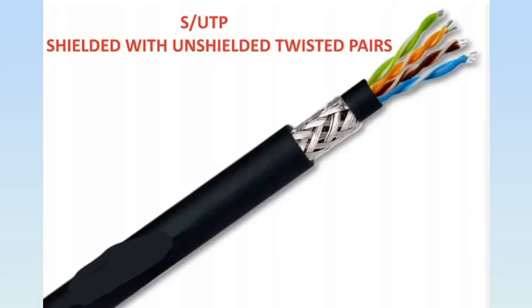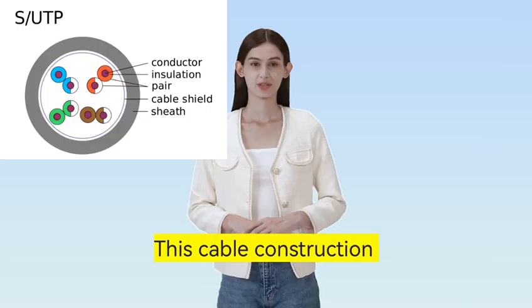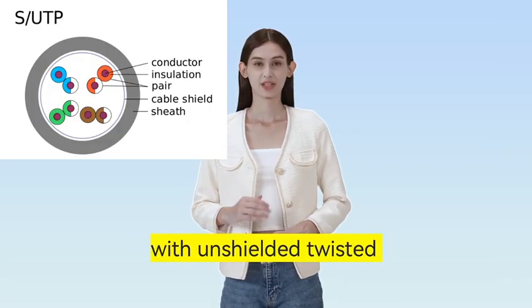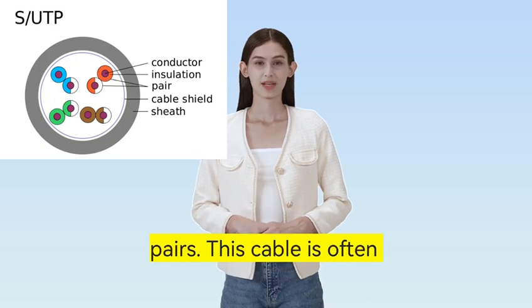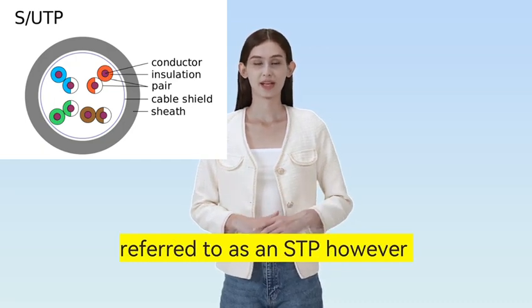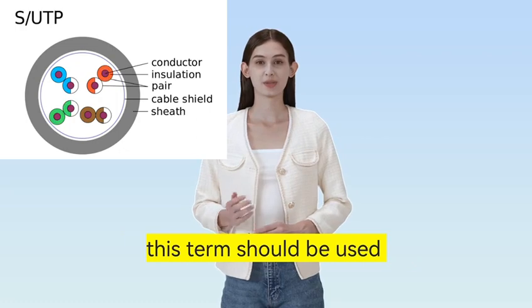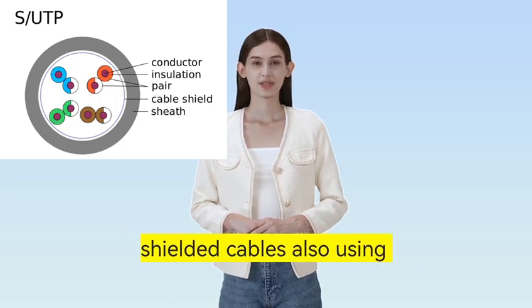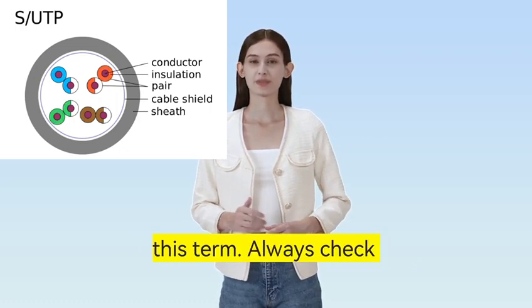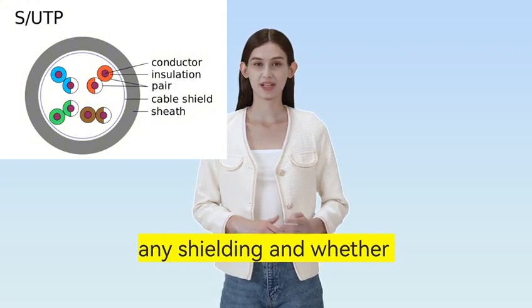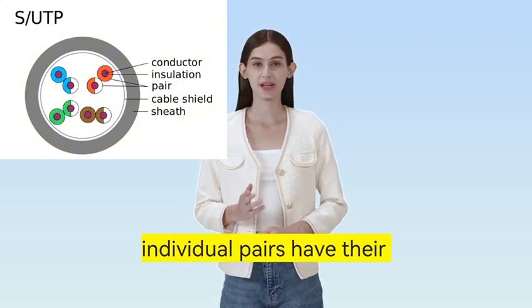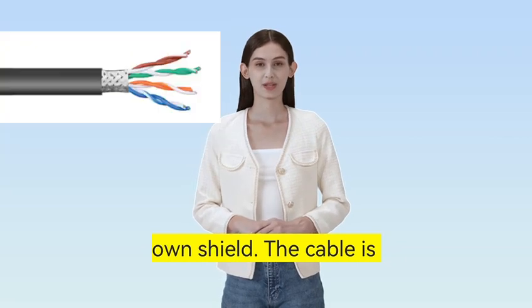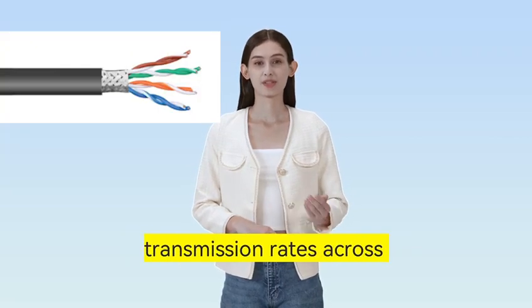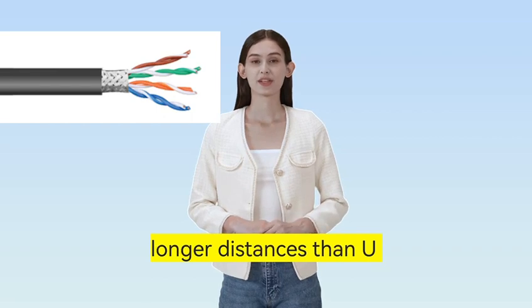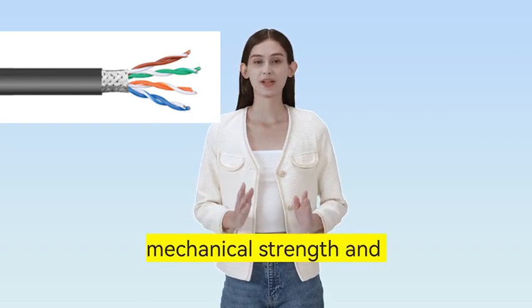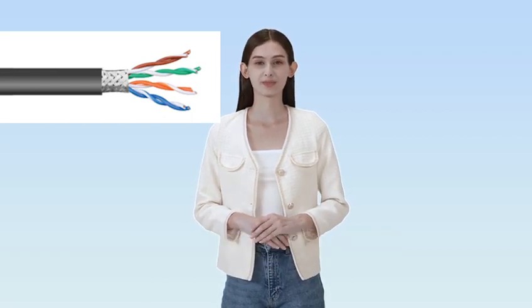S/UTP, shielded with unshielded twisted pairs. This cable construction has an overall braid screen with unshielded twisted pairs. This cable is often referred to as an STP, however this term should be used with caution due to other shielded cables also using this term. Always check whether the cable will have any shielding and whether individual pairs have their own shield. The cable is capable of supporting higher transmission rates across longer distances than U/UTP and provides better mechanical strength and grounding due to the braid.